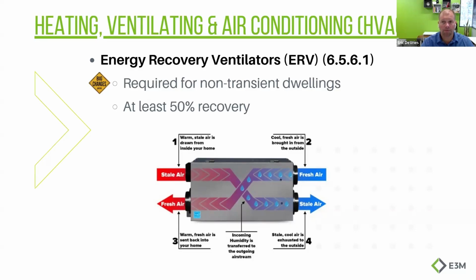Right? All of us design professionals, we used to bring some fresh air, stick it into the side of a furnace, stick it into the back of a PTAC, stick it into a magic pack, and say, hey, we're getting our fresh air requirements that way. This code does not allow that. You have to have an ERV on that fresh air and that exhaust air for a non-transient dwelling that has at least 50% energy recovery.